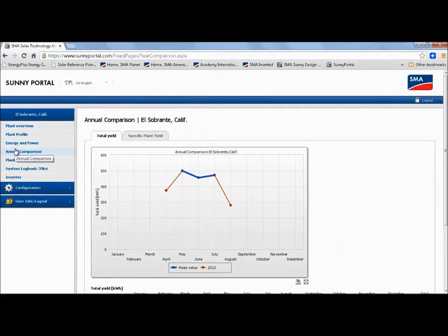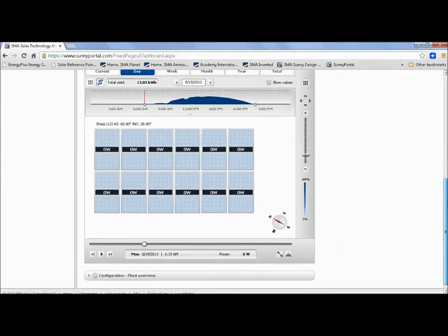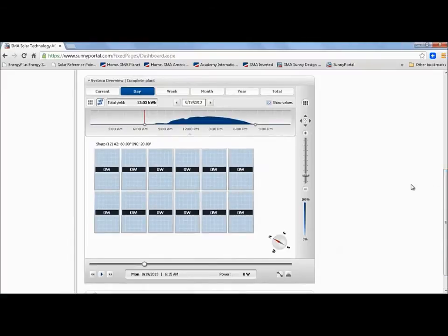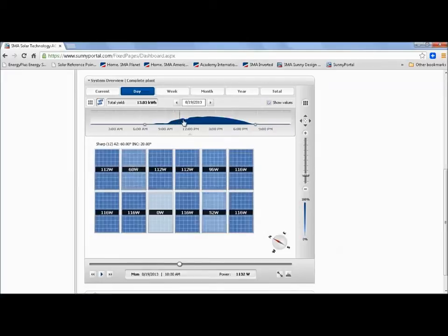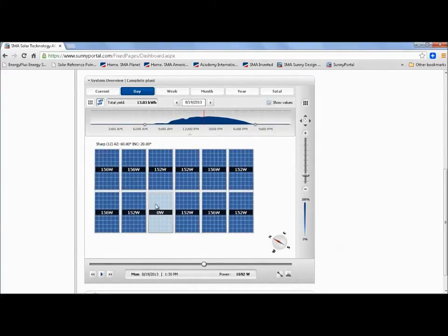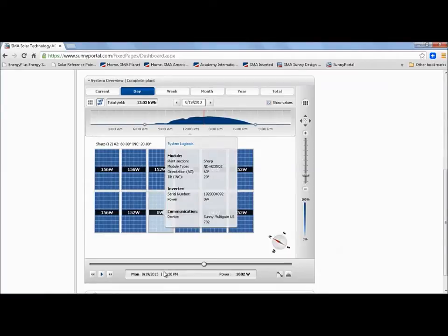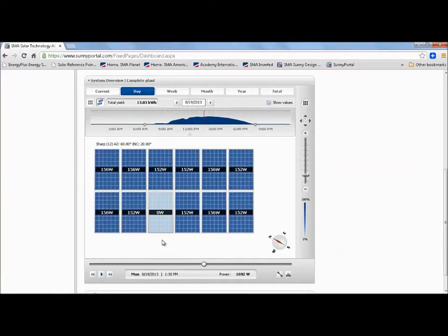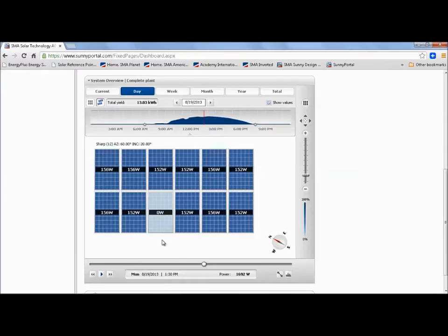What I want to show you now is the system overview back in the plant profile if you have an inverter that isn't operating correctly. So here I've scrolled down into the system overview. And what I'm going to do is move the red line over into our profile here of the day. And here we see an inverter that is showing zero watts. This inverter has been disabled for this video to show you what it would look like if your inverter is bad. So this is invaluable information. This is down time of that particular inverter. The installer would be able to service this inverter by responding to the email from the Sunny Portal that something is not right.